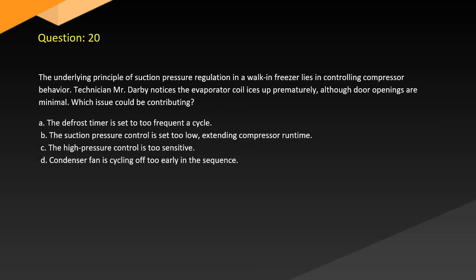Question 20. The underlying principle of suction pressure regulation in a walk-in freezer lies in controlling compressor behavior. Technician Mr. Darby notices the evaporator coil ices up prematurely, although door openings are minimal. Which issue could be contributing? A. The defrost timer is set to too frequent a cycle. B. The suction pressure control is set too low, extending compressor runtime. C. The high pressure control is too sensitive. D. Condenser fan is cycling off too early in the sequence.